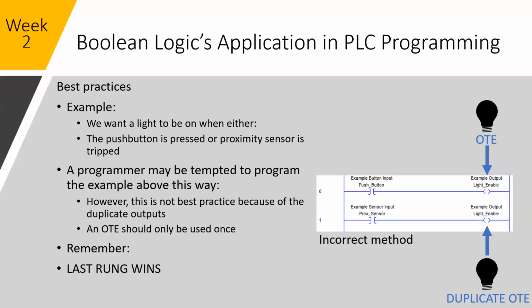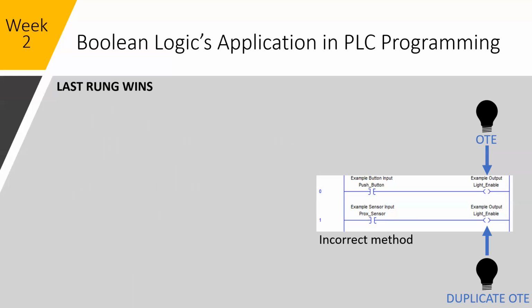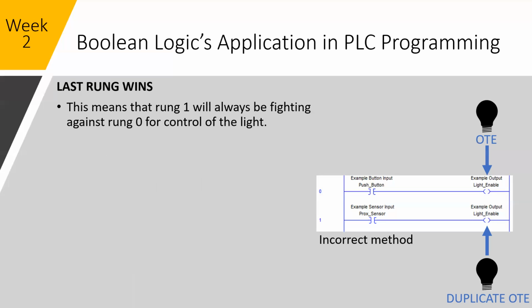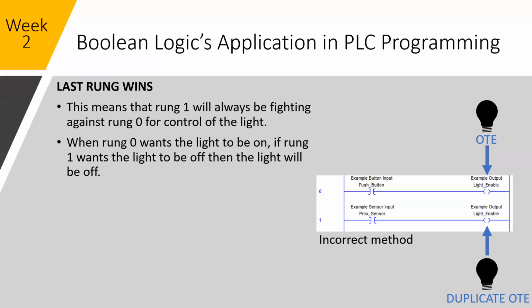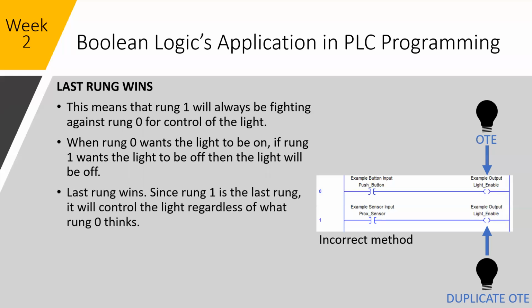So last rung wins. So whatever is happening further down the line is the last state that this bit bool will be in. Again, this is just reiterating what I said. Last rung wins. This means that rung 1 will always fight with rung 0 for control. When rung 0 wants the light to be on, if rung 1 wants the light to be off, it will be off.